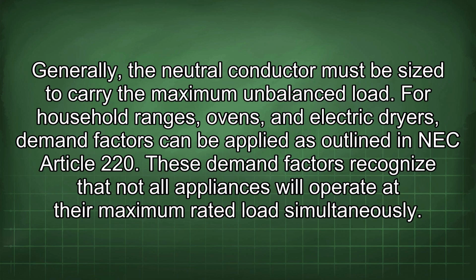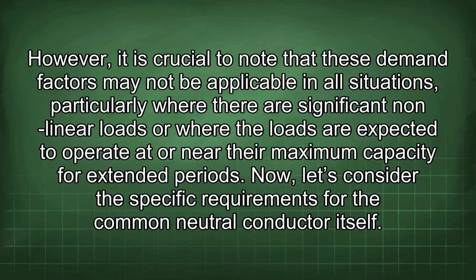For household ranges, ovens, and electric dryers, demand factors can be applied as outlined in NEC Article 220. These demand factors recognize that not all appliances will operate at their maximum rated load simultaneously. However, it is crucial to note that these demand factors may not be applicable in all situations, particularly where there are significant nonlinear loads or where the loads are expected to operate at or near their maximum capacity for extended periods. Now, let's consider the specific requirements for the common neutral conductor itself.